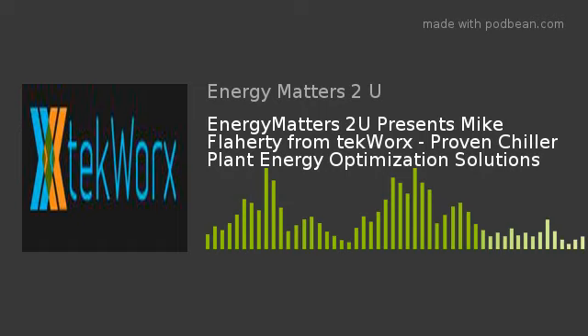One strategy we've developed extensively, because of our industrial automation background, is known as adaptive control, where we're making continuous changes while the system operates, without a human getting in there and tweaking everything. The optimization algorithms pick the most efficient combination of equipment, determine the most efficient set points for temperatures and pressures, and make sure the building automation system receives that information to make intelligent, energy-effective operational decisions. That's the second area.